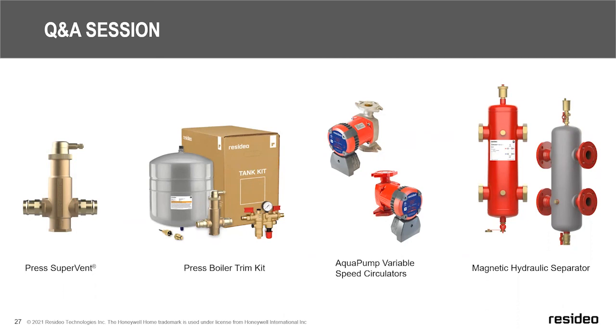And the other thing I'll bring up too, with the variable speed pumps, a lot of times you don't even have to control them. I didn't talk on this, but these pumps can do what's called deadheading. Meaning, if you had an old 3-speed pump, you essentially had to have somewhere for that water to go. That's why we always had to give it an on-off switch, and I'm talking about the system side. So let's say we had 6 zone valves. You had to have at least one of them open for that pump to turn on. And that's really the predominant reason we used end switches.